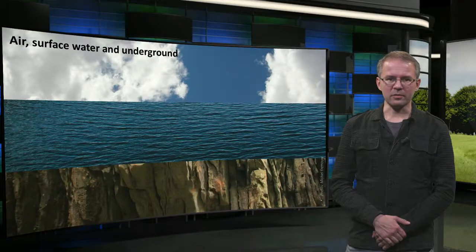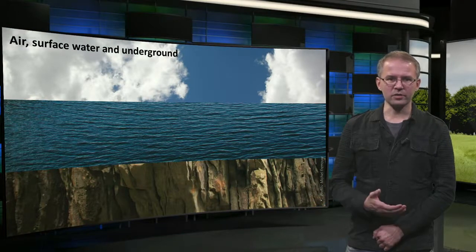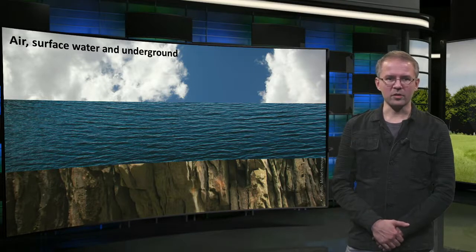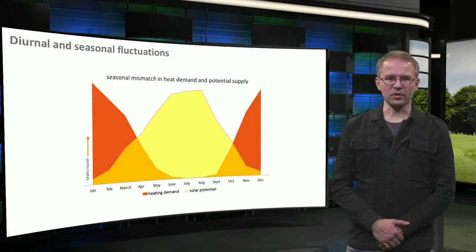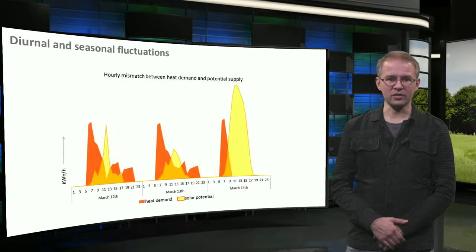Each of these sources has a working mass and a temperature, and we can use them to either draw heat or release it into the medium for cooling. The temperature of most of these sources is low, so usually you will need a heat pump to upgrade the heat or cold for part of the year. Most of these sources fluctuate both diurnally and seasonally, meaning they will be a lot more effective if you can store the energy — either heat or cold — for use in the off period.